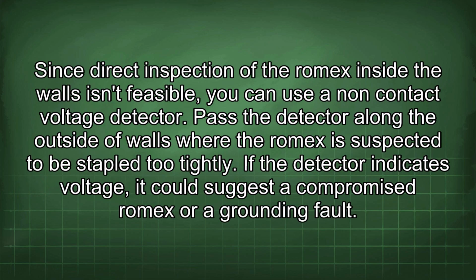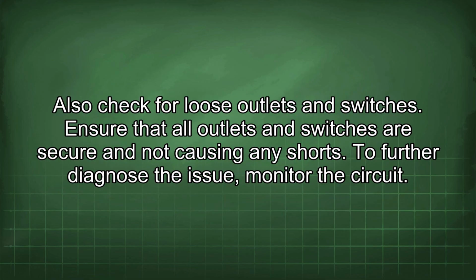Since direct inspection of the Romex inside the walls isn't feasible, you can use a non-contact voltage detector. Pass the detector along the outside of walls where the Romex is suspected to be stapled too tightly. If the detector indicates voltage, it could suggest a compromised Romex or a grounding fault. Also check for loose outlets and switches. Ensure that all outlets and switches are secure and not causing any shorts.